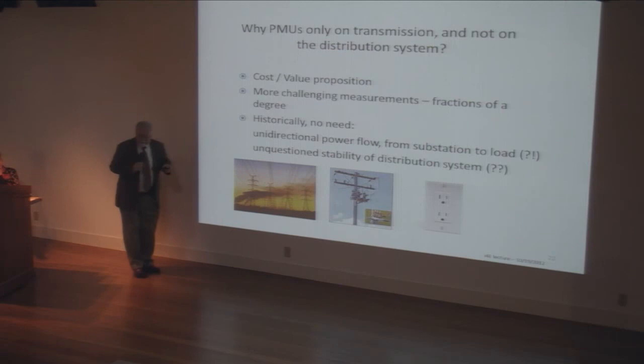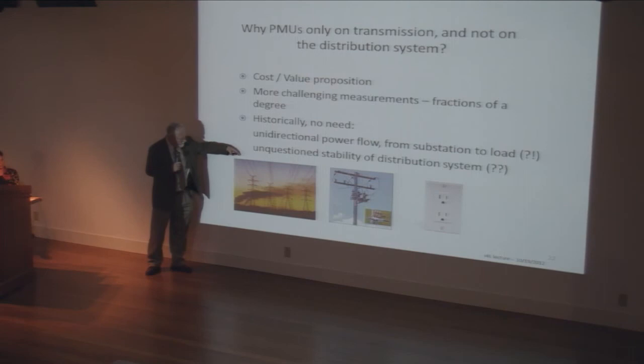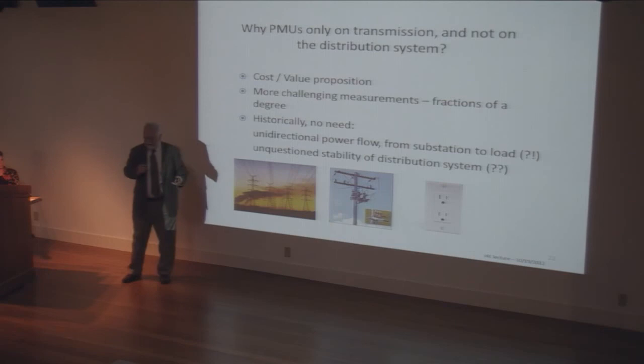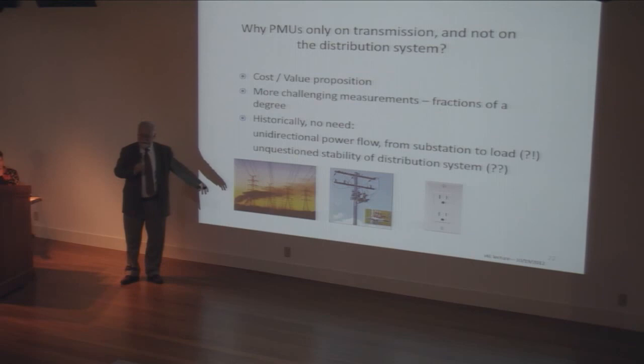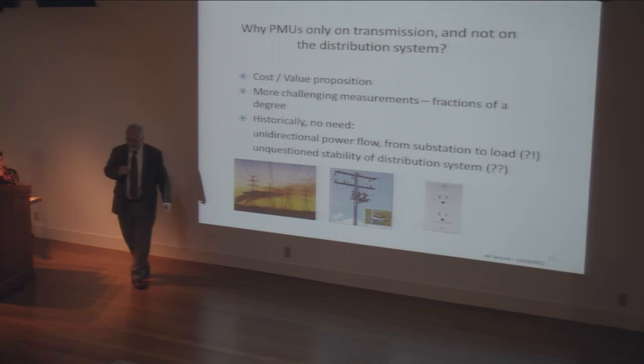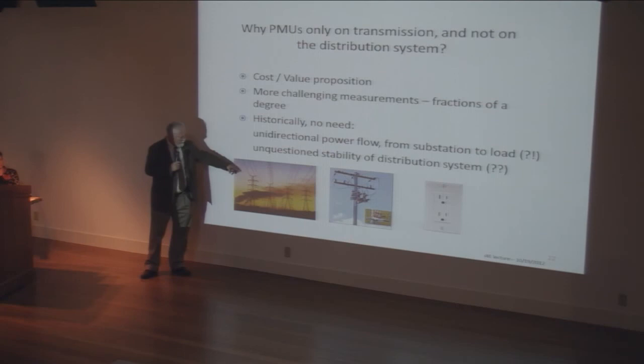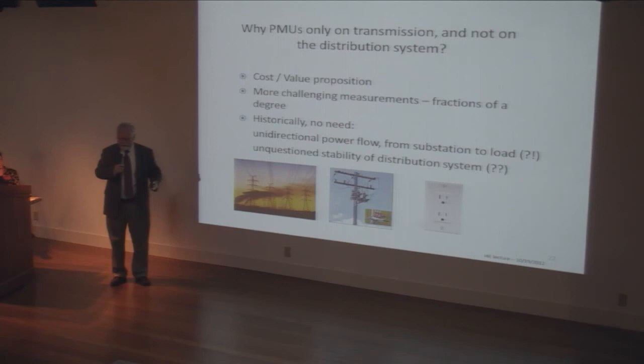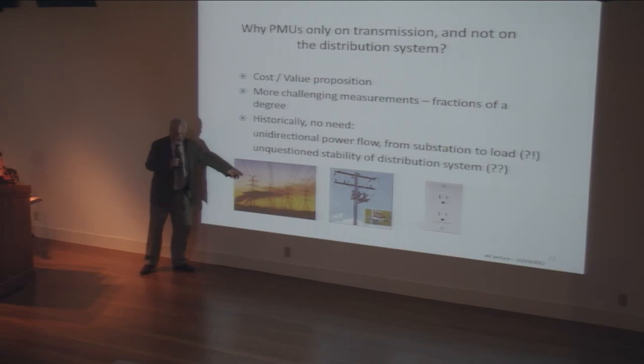The other challenge on distribution is that, as Sascha said, all of the phase angles are introduced by the inductance of these conductors. The inductance is roughly linearly proportional to the distance between the conductors, and it's an order of magnitude bigger here than there. So the inductances we're dealing with on the distribution system are a couple to three orders of magnitude smaller, meaning the phase angle differences are also three orders of magnitude smaller. A thousandth of a degree is interesting, as opposed to a degree on these systems.